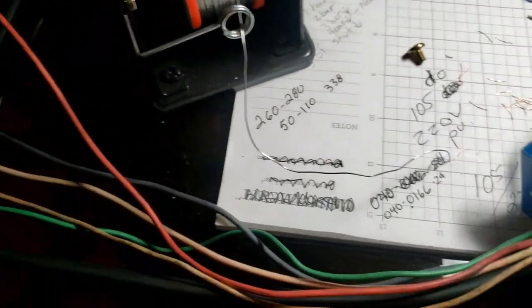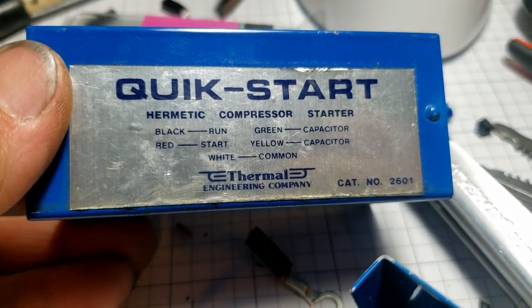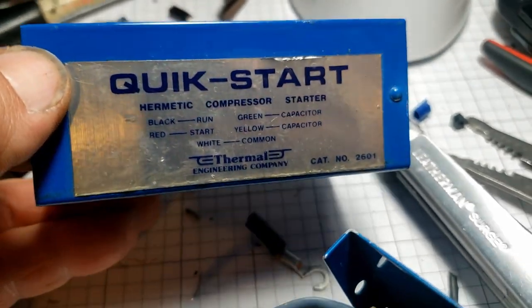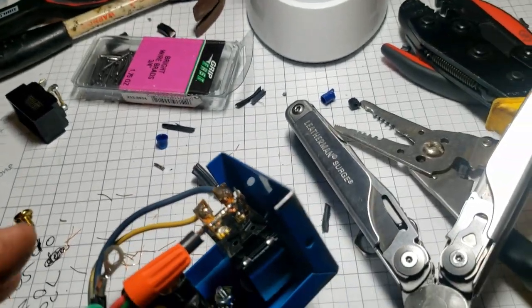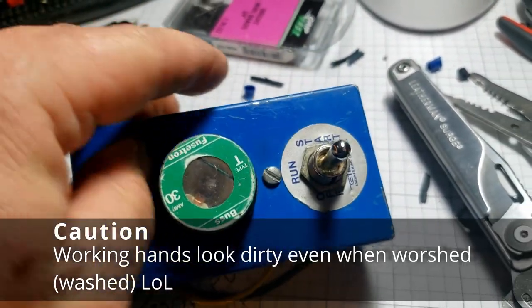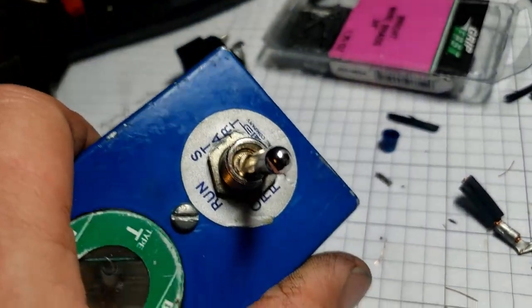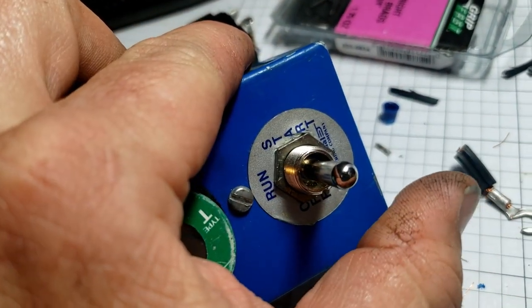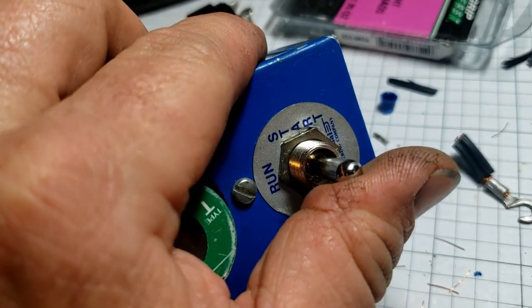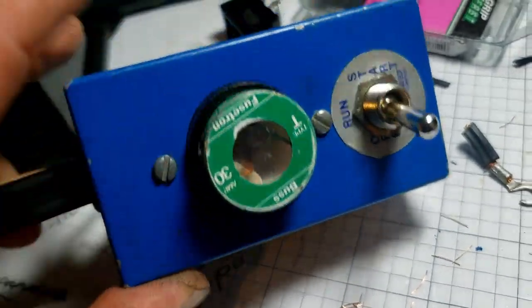I just finished working on my Quick Start by Thermal Engineering Company - this is an expensive little hard start kit for testing compressors. You can actually do a full size compressor. The problem with this one was the switch was defective. It starts out with off, then run, then start, which puts the capacitor in the circuit. You let it off and it continues to run, shut it off. There's a 30 amp fuse in here.